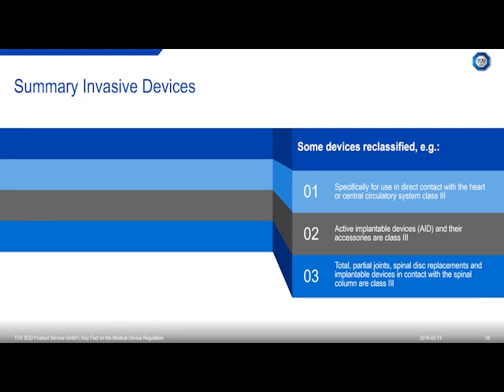Then there are active implantable devices, which were up until now under the AIMDD. They are now class 3 in the MDR. And we will have a class 3 classification for all total or partial joint replacement, spinal disc replacement, and implantable devices in contact with the spinal column. All joints. Also a joint that is only in your fingers or in your small finger. That is a total joint replacement. It is there for a certain while, which is years, decades, and therefore it's a class 3 device. That is something that is new. It's not only focusing on hip or knee replacements.